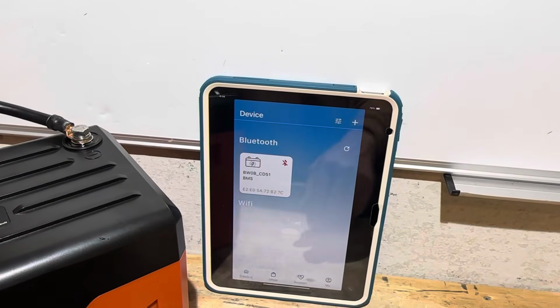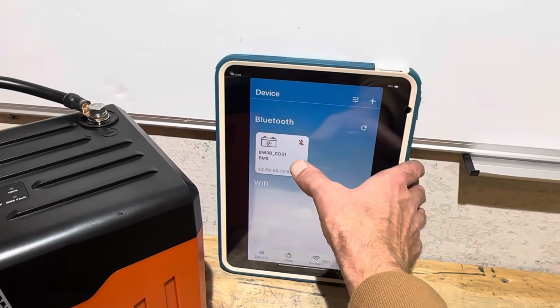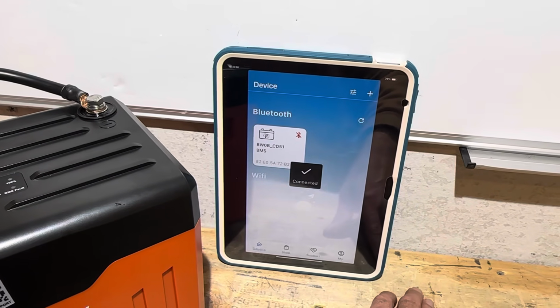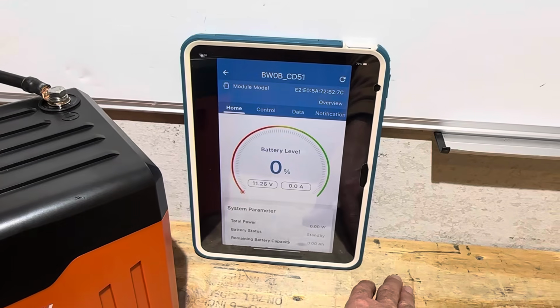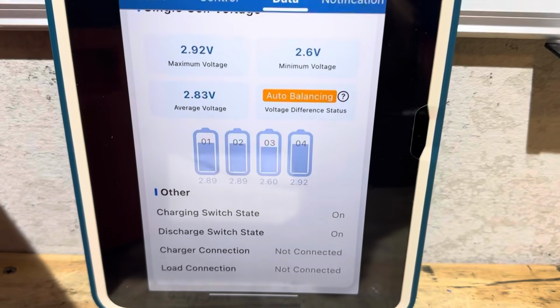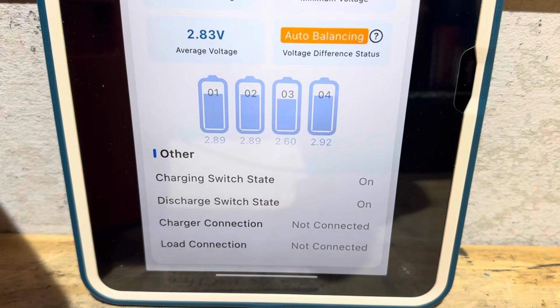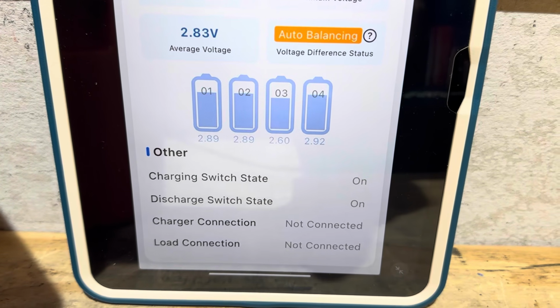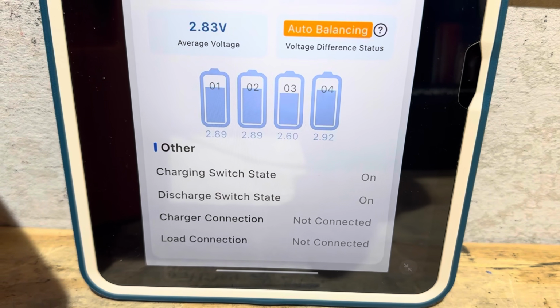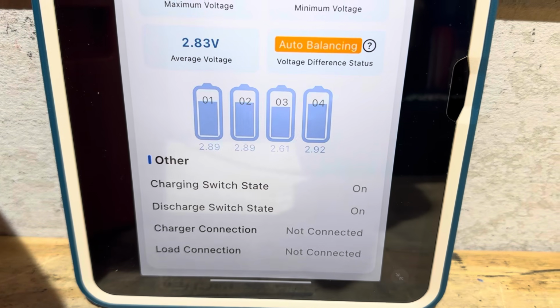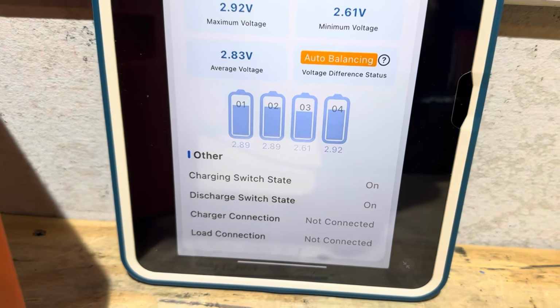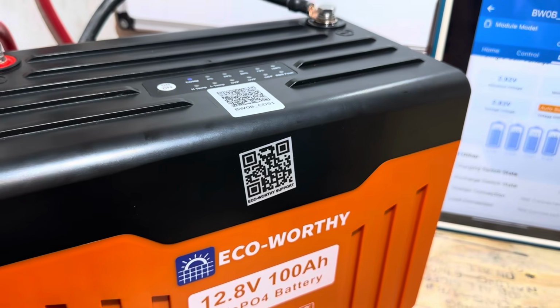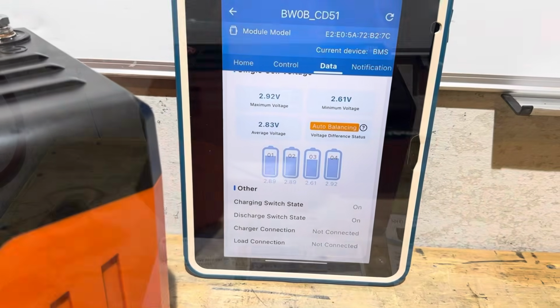Now let's see if the Bluetooth will reconnect now that the BMS came back up on the battery. Let's see if we can get it back. All right, we got it back. Once the data came back up for the Bluetooth monitoring, you see cell 3 is at 2.6 right now. Most protection strategies, the cells are 2.5 volt minimum, and you saw that cell was below 2.5, so we're going to run with that - this BMS triggered on cell number 3.